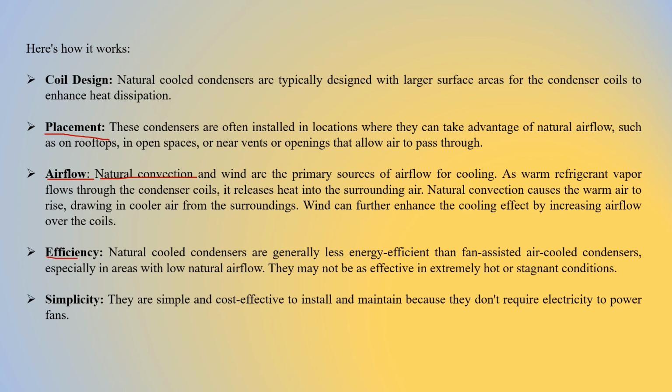And the efficiency: the efficiency is generally very low, because there is no forced convection. And the simplicity: it is very simple and cost effective, and it is easy to install and maintain because it does not require any electricity to power fans. So they are easy to install and maintain, and cost effective. This was all about natural air cooled condensers.